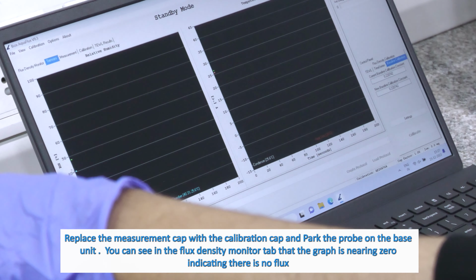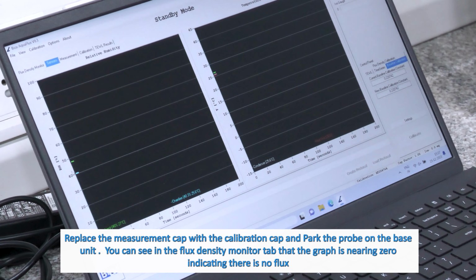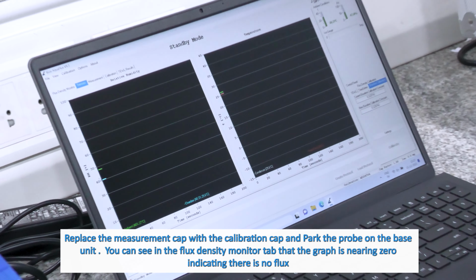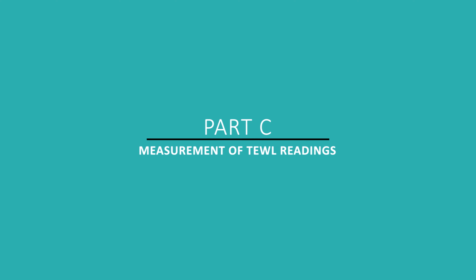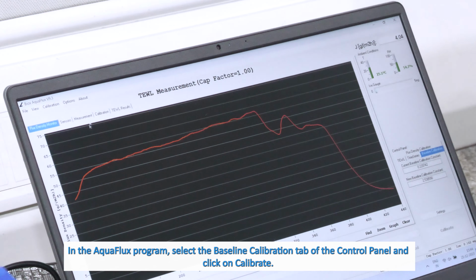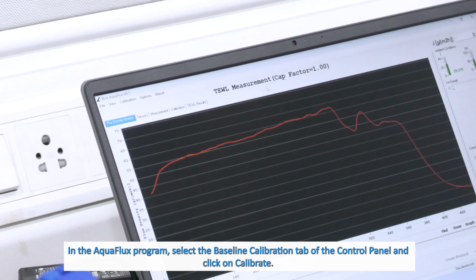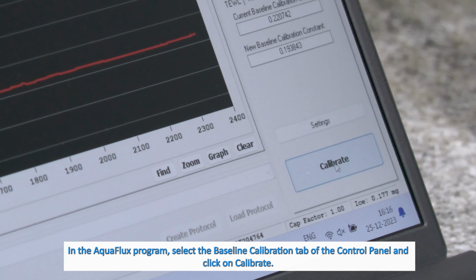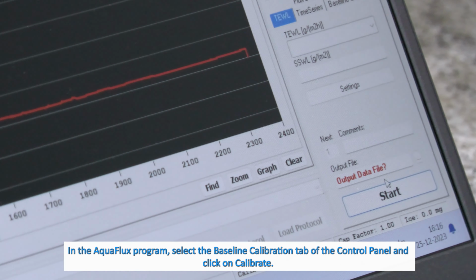You can see in the flux density monitor tab that the graph is nearing zero, indicating there is no flux. Wait for at least 30 minutes until the flux readings have settled to a steady level. In the Aquaflux program, select the Baseline Calibration tab of the control panel and click on Calibrate.